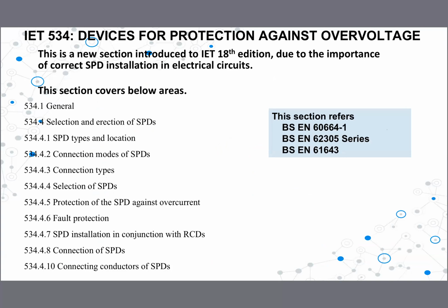534. In part 5 of the IET regulation, part 5 is the selection and erection of equipment. Under this part 5, chapter 3, 4, you can find a separate clause, a separate section for devices for protection against overvoltage, right? There it is clearly mentioned. This was not in the 17th edition, right? In the 17th edition, it was blank, but in the 18th edition, it is clearly given. So it says you have to follow these parts in your design, right?